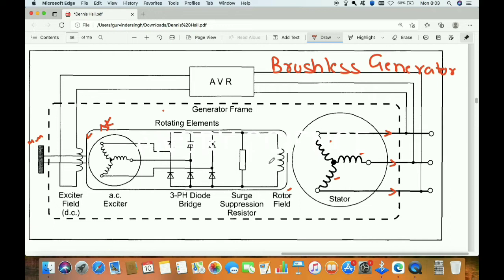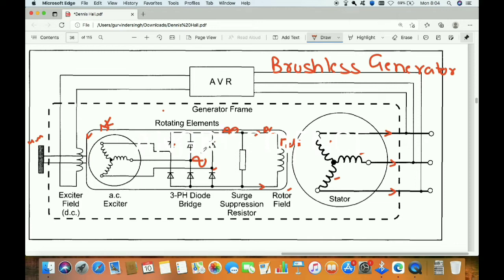This field is normally produced by a DC supply, so we need DC here. How can we get DC without conducting any external wiring? The DC comes to the field conductor and produces a field. This DC comes from a diode, which converts AC into DC. So up to the diode we have AC supply, and after the diode we get DC supply. This AC is produced by a conductor here that is producing an EMF which is AC in nature.